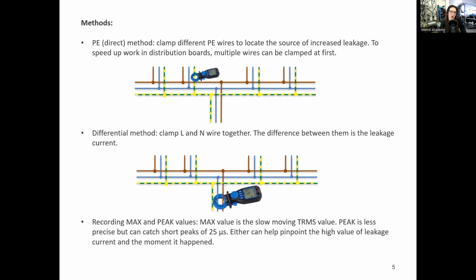However, this method has a mild disadvantage. Some current is going to leak away from the part of the installation where we are trying to measure and only end up in the collector PE wire. So when we are looking for the location where our leakage happened, we may not find it. Usually, if this disadvantage turns up, we have an installation that does not have very well insulated walls or floors. However, most installations are isolated enough that this does not happen. This is not such a big problem. However, if it turns out to be, if we cannot find the location of our leakage using the PE wires, we have the second method available.